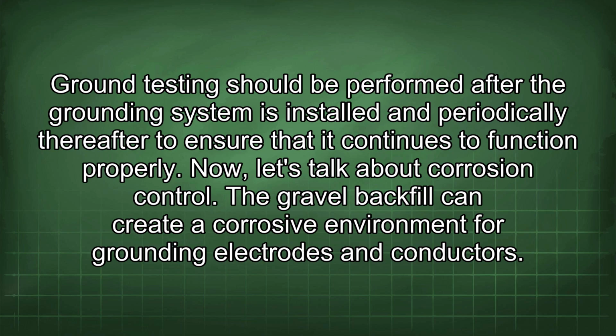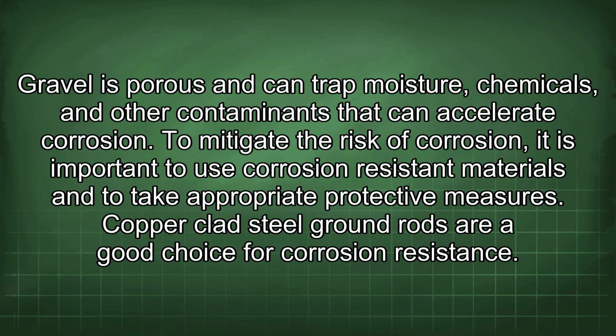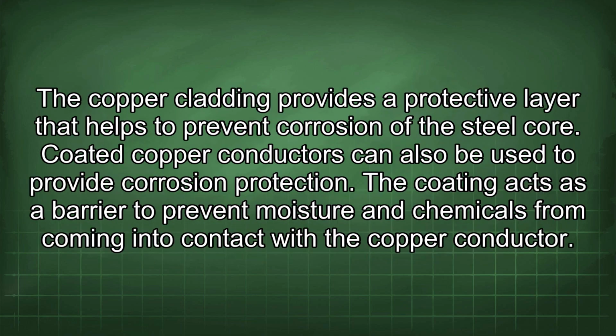Now let's talk about corrosion control. The gravel backfill can create a corrosive environment for grounding electrodes and conductors. Gravel is porous and can trap moisture, chemicals, and other contaminants that can accelerate corrosion. To mitigate the risk of corrosion, it is important to use corrosion-resistant materials and to take appropriate protective measures. Copper-clad steel ground rods are a good choice for corrosion resistance. The copper cladding provides a protective layer that helps to prevent corrosion of the steel core.